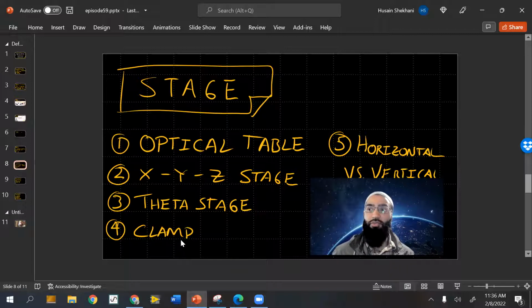That's why, honestly, the stage is so important to have a long stage range, because after you clamp your transducer and put it in some type of foam and you're testing it for its displacement, you're not easily going to be able to control exactly where it sits. You'll need to tape it down with something. A good option would be taping it down lightly to a piece of foam, which is maybe stuck to another platform. You could hot glue your foam to a small platform, and then put your transducer on there and find some way of taping it down temporarily, so that you won't have disturbance of its resonance. But the best thing is to have that clamp incorporated into your transducer already, so then you won't have trouble holding it.